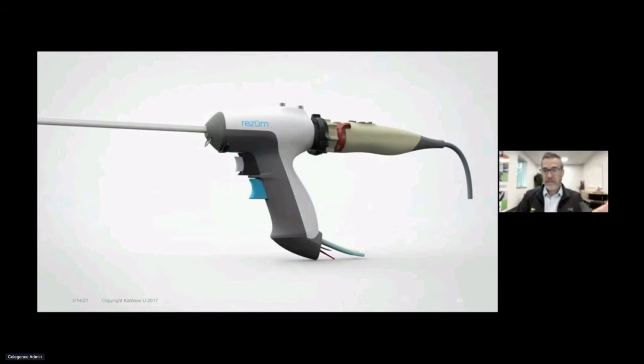We would do verification and validation in your design controls, but from a usability standpoint, we would do our usability validation with this device through what we call a summative study. This is where we get 15 or more users. They all use this device in a real world situation. And we document whether all of those potential use hazard situations are mitigated and are acceptable at the end of their use. We record that, and we have a usability report that comes out of a summative study. And then we have a usability engineering report that sums up the entire thing at the end.